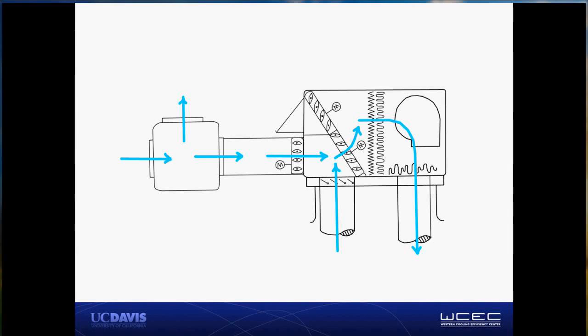The best way you can think about it is that if that product plenum is under negative pressure, you can start to cause some imbalance in the airflow between the primary and secondary channels, and even perhaps draw air backwards through the secondary channels, which is not what you want to do.